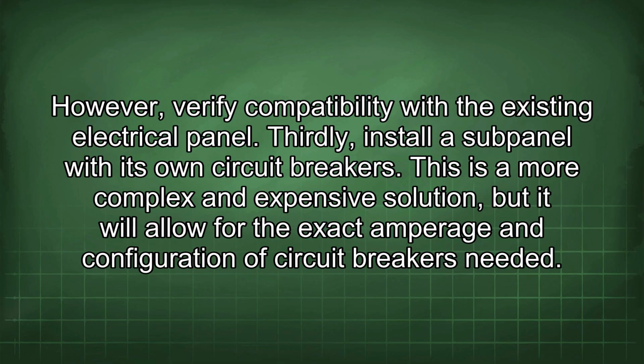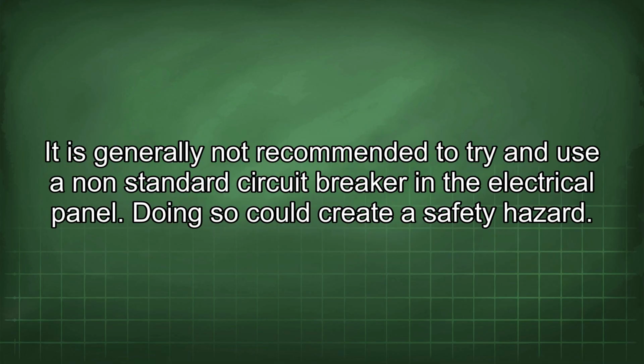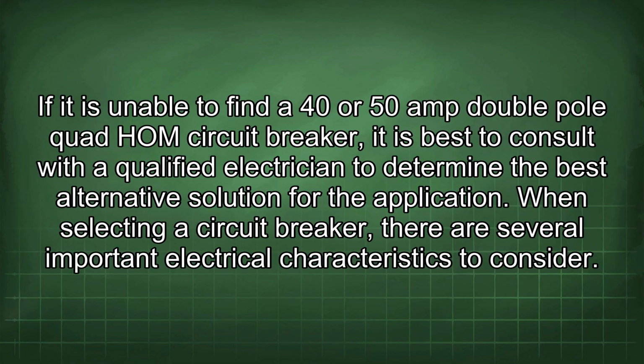Thirdly, install a subpanel with its own circuit breakers. This is a more complex and expensive solution, but it will allow for the exact amperage and configuration of circuit breakers needed. It is generally not recommended to try and use a non-standard circuit breaker in the electrical panel. Doing so could create a safety hazard. If it is unable to find a 40 or 50 amp double pole quad HOM circuit breaker, it is best to consult with a qualified electrician to determine the best alternative solution for the application.